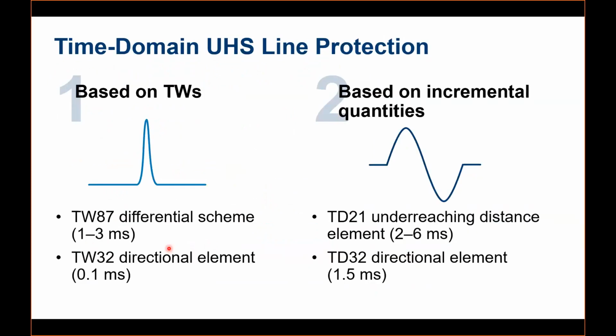A little bit on the time performance of the relay. TW87, the differential element, may act in 1 to 3 milliseconds. Plus, it depends on the line length. If your line is very, very long, like more than 300 kilometers, you can add just a couple of milliseconds more in that time. But ideally, it should operate in less than 3 milliseconds. It's very consistent.